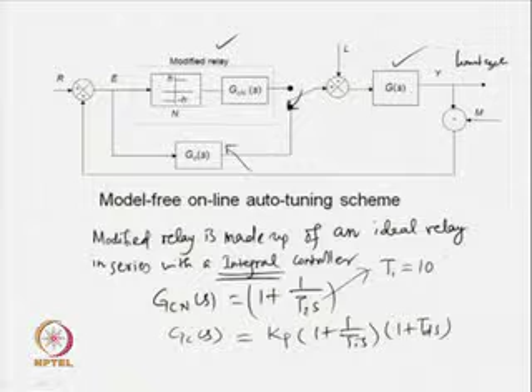So, initially, when you are starting a process or commissioning a process, you have no information about the process. So, during that time, to initiate the relay test, what will be done? The Ti, the integral time constant, can be set to certain values, like choose from 10 to 20, when of course the process G(s) is stable. So, when G(s) is a stable process, please choose or set the value for Ti from 10 to 20, choose any value from 10 to 20, and then you conduct the relay test.